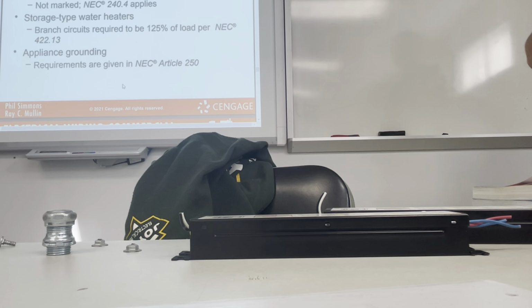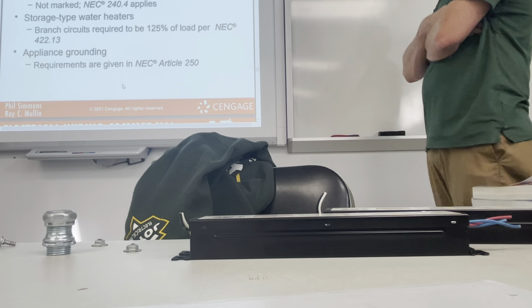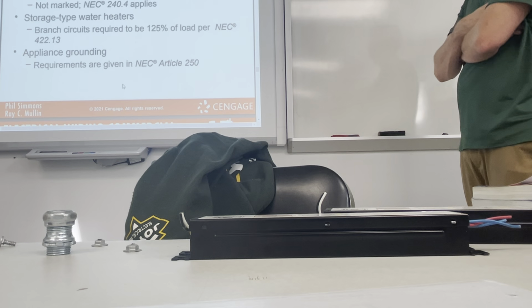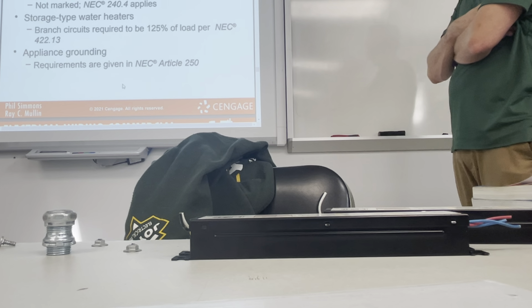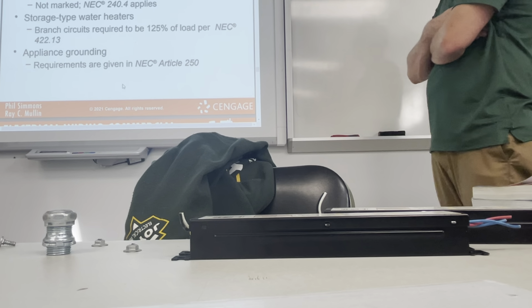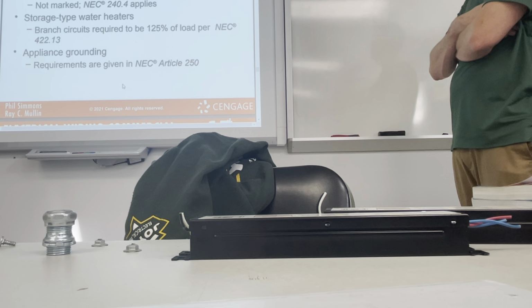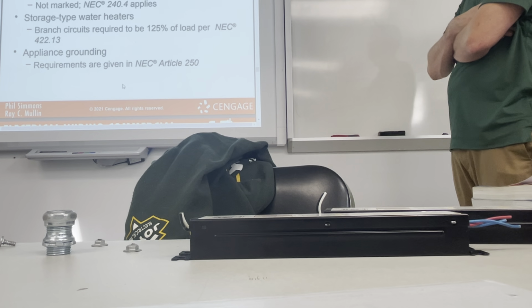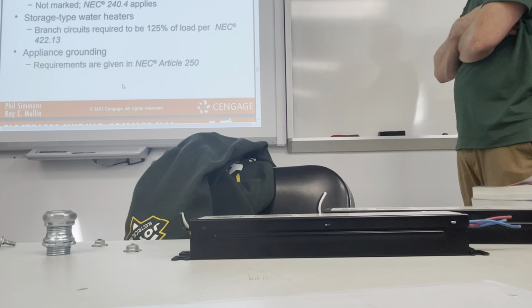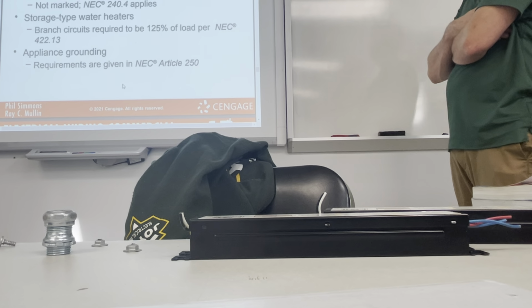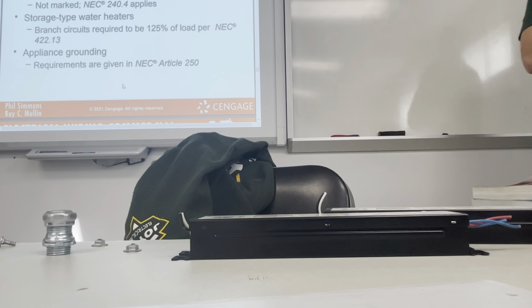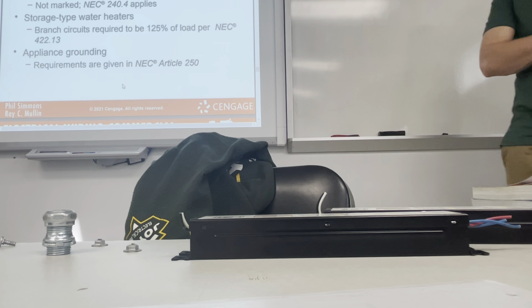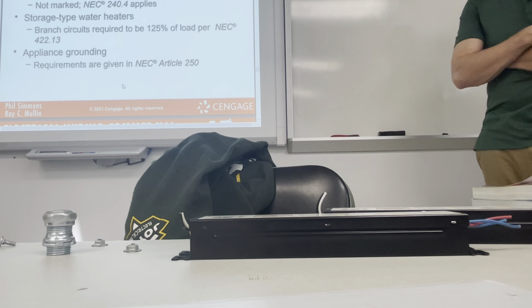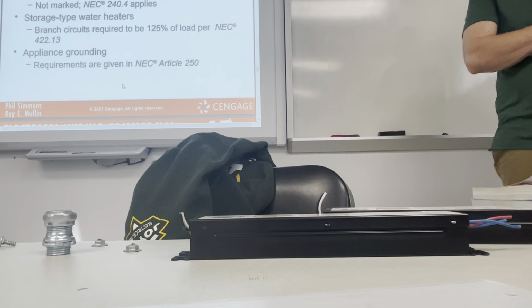Appliance branch circuit overcurrent protection. Marked with maximum size of protection device. Not marked, NEC 240.4 applies. Storage type water heaters: branch circuits required to be 125% of load per NEC 422.13. Appliance grounding requirements are given in NEC Article 250. But most appliances are going to have a nameplate on them that tells you how many amps they pull. And some, especially air conditioners nowadays, will tell you a minimum and maximum service size.